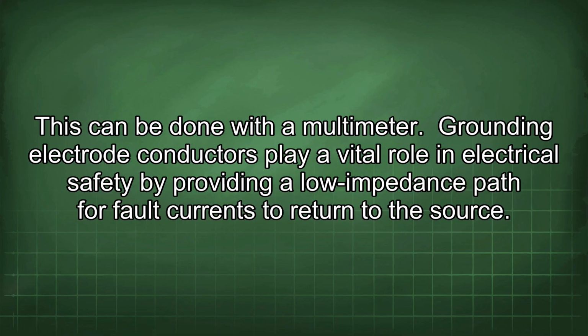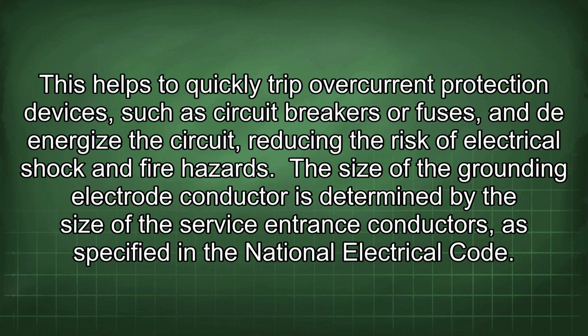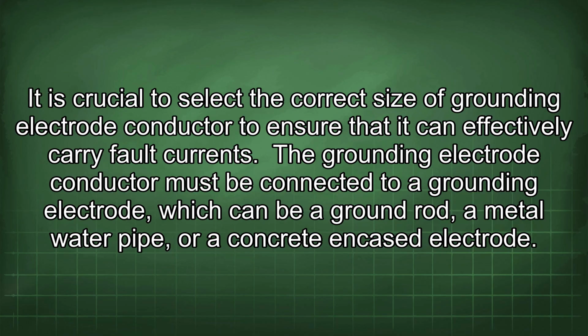Grounding electrode conductors play a vital role in electrical safety by providing a low impedance path for fault currents to return to the source. This helps to quickly trip overcurrent protection devices, such as circuit breakers or fuses, and de-energize the circuit, reducing the risk of electrical shock and fire hazards. The size of the grounding electrode conductor is determined by the size of the service entrance conductors, as specified in the National Electrical Code. It is crucial to select the correct size of grounding electrode conductor to ensure that it can effectively carry fault currents.